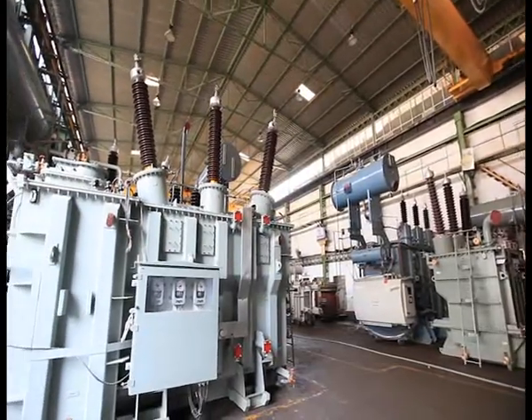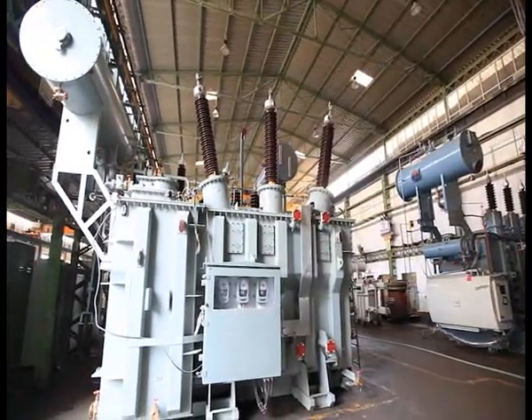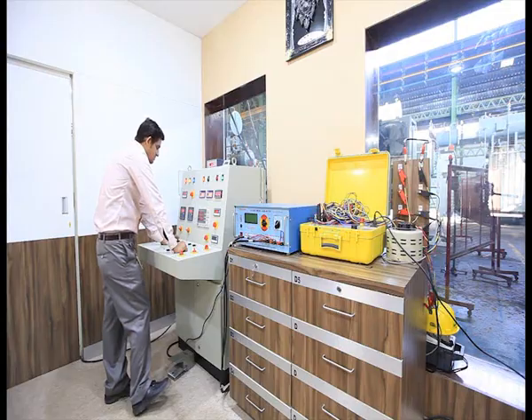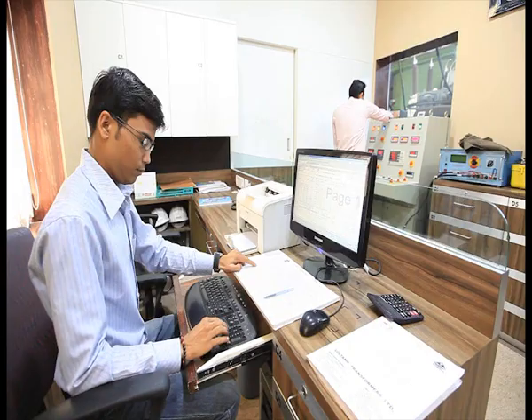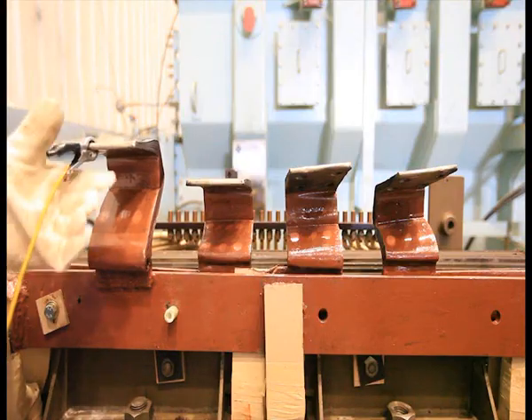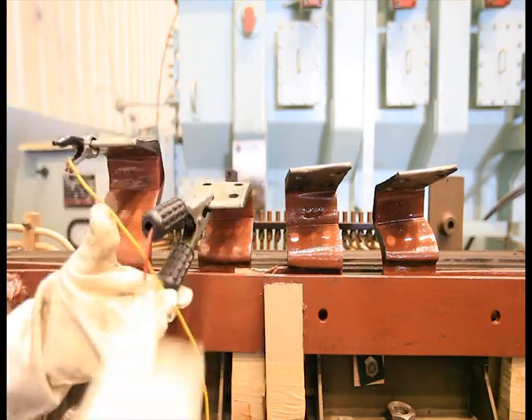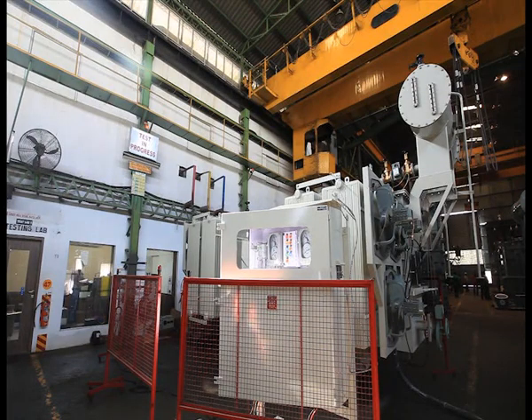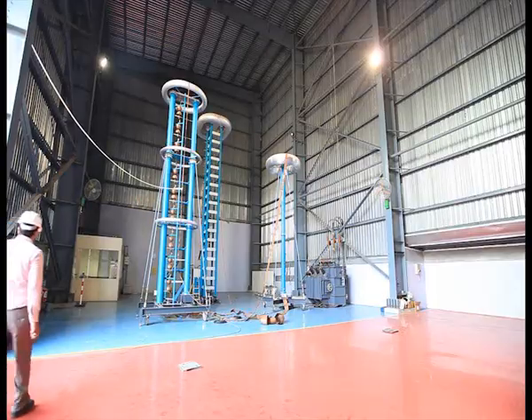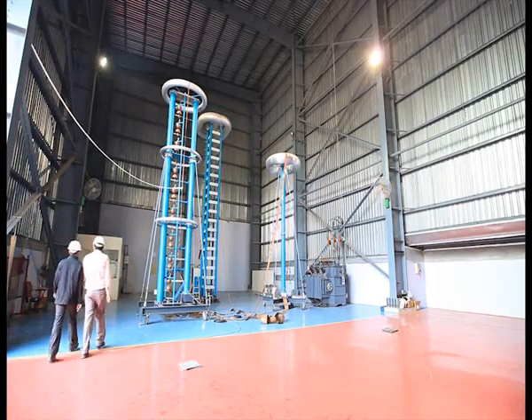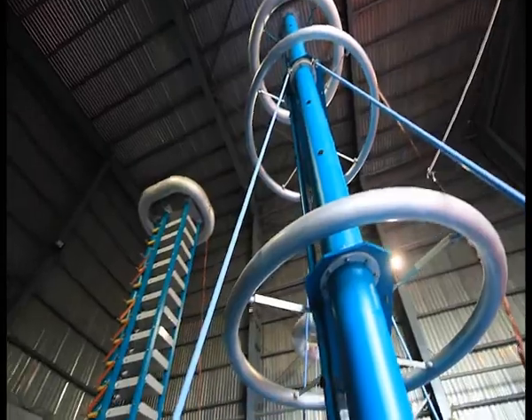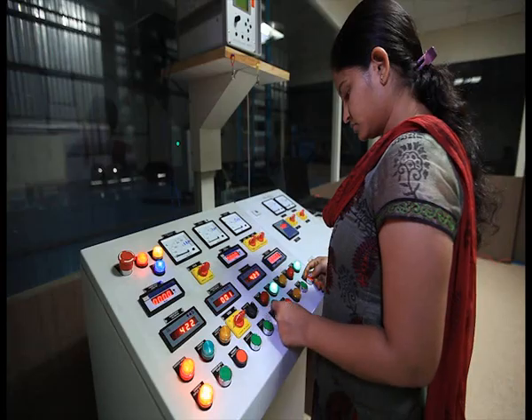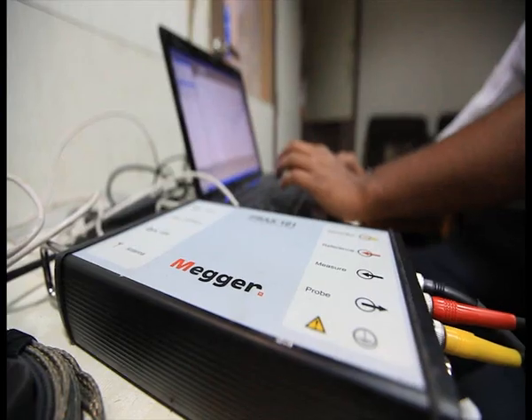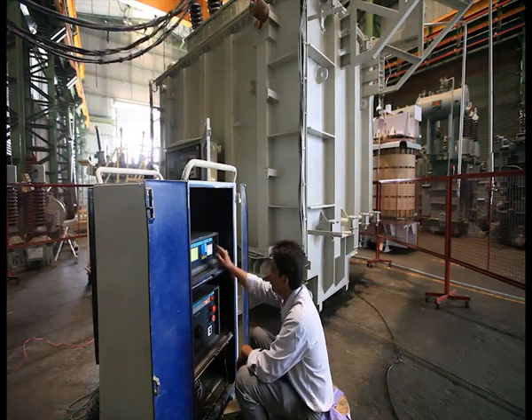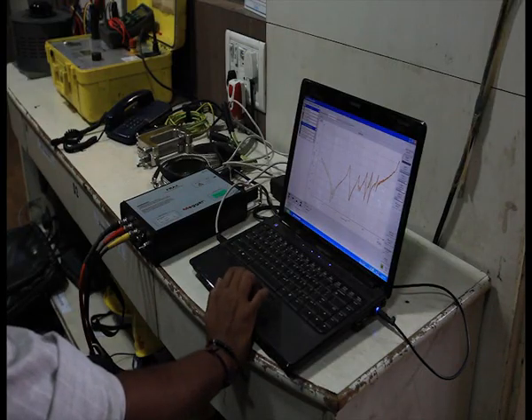Just as a newly manufactured transformer is subjected to various tests, all repaired transformers also pass through well-defined process norms, stage tests, quality checks and final testing in our NABL accredited test laboratory. We are also equipped with an Impulse Test Laboratory. Type and special tests such as impulse, partial discharge, heat run, SFRA, capacitance and tan delta are conducted in-house on customer request.